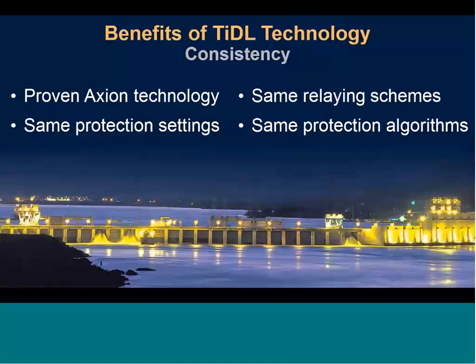Some of the other benefits of TiDL are with consistency. To talk about the proven Axion technology, we introduced the Axion in 2011. We've used it in harsh environments and critical applications, so we know it's a very reliable platform, and it also brings us some nice modularity. We can leverage that proven technology to make our application flexible and still work anywhere and be reliable. From the relay side, essentially the relays are unchanged. The protection settings are the same today as what you would have in a hardwired relay, and they're still running the same algorithms, so we can apply the same schemes. Essentially, we just have to change how we're getting our wiring, but from a settings and protection scheme standpoint, nothing should change.